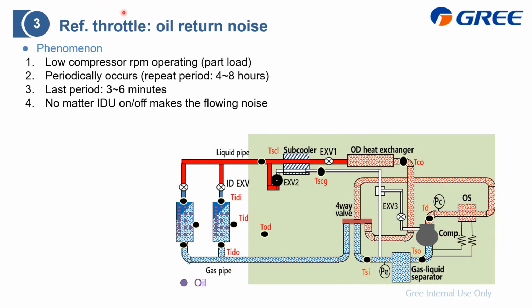Refrigerant throttle or metering. This time we are going to talk about the oil return noise. First is the phenomenon. The first one is low compressor RPM operating, especially in part load condition, which means you just turn on 1/3 or 1/4 of the indoor units, and you make the system operate under the low load condition. For example, the outdoor is already 23 or 22 degrees, and you also need to turn on cooling. Then the system will operate in part load, which means the compressor is in low RPM.